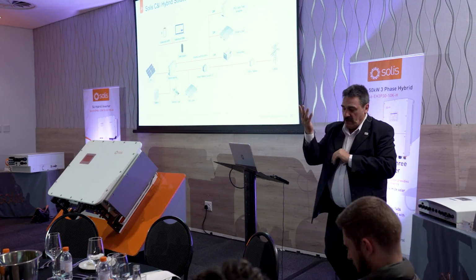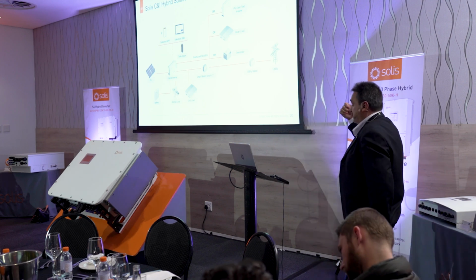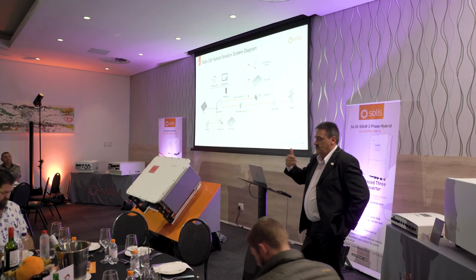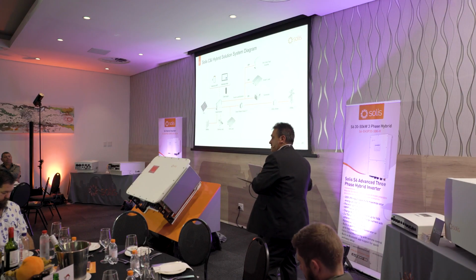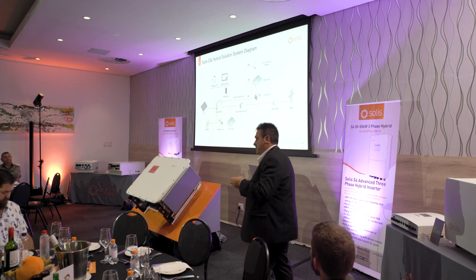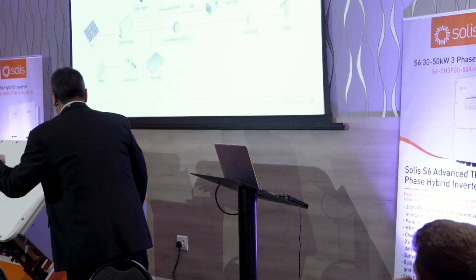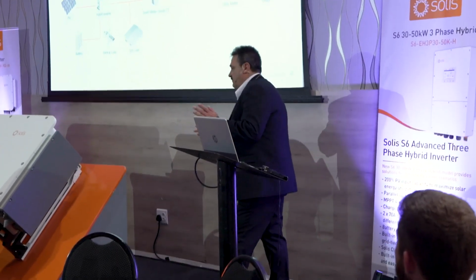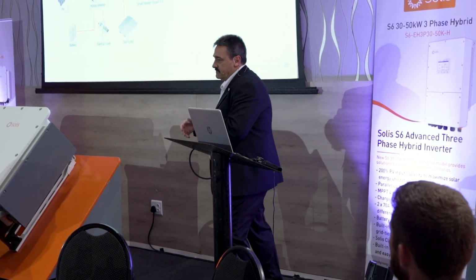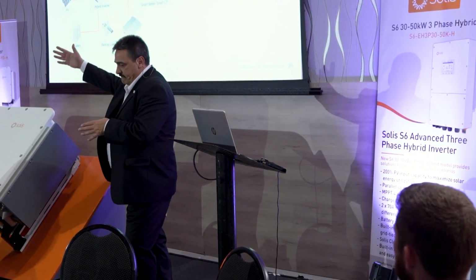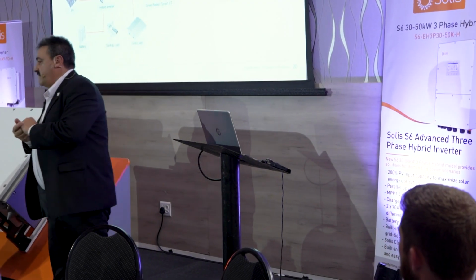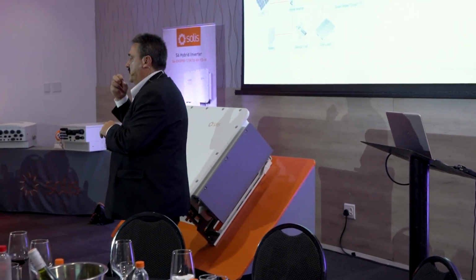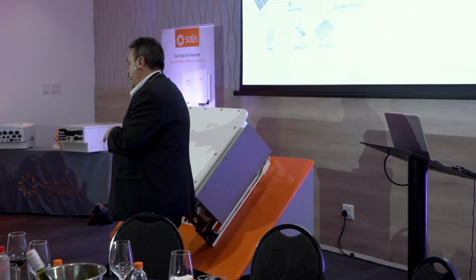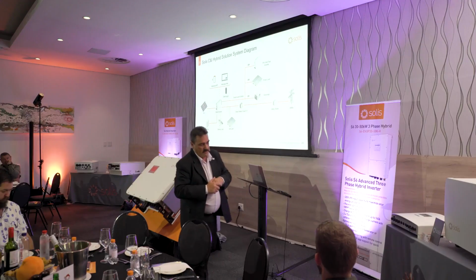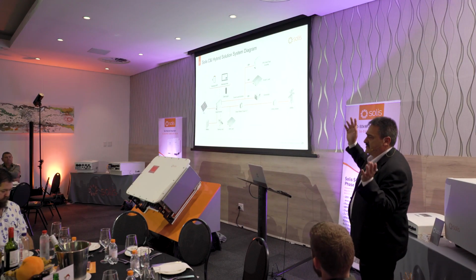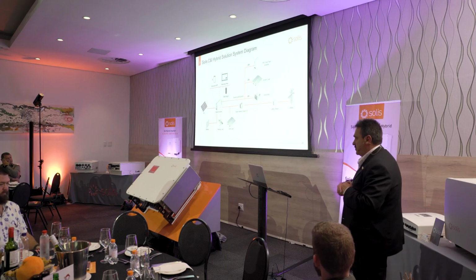When you AC couple a grid-tied inverter to the AC couple port, the inverter will react to frequency shifting when the system goes into backup. It will be controlled by shifting frequency. Normally it starts at 50.5 hertz, and at that point it will ask for maximum power from the grid-tied system. It then slowly progresses up to 52.74 hertz, and at that point it will tell the system it doesn't need any more PV power, so it will slow it down. This is completely automatic, nobody needs to touch it, and for safety it cuts off around 53 hertz, which completely shuts it down.